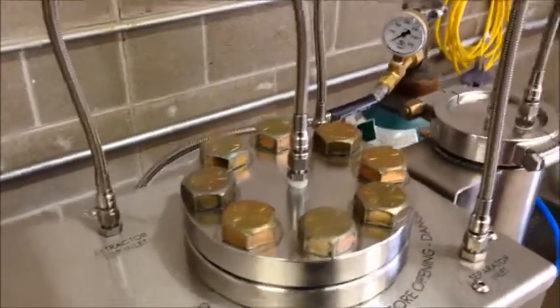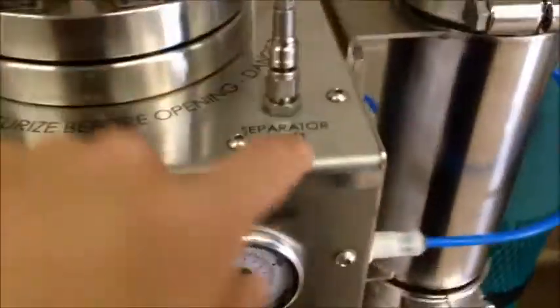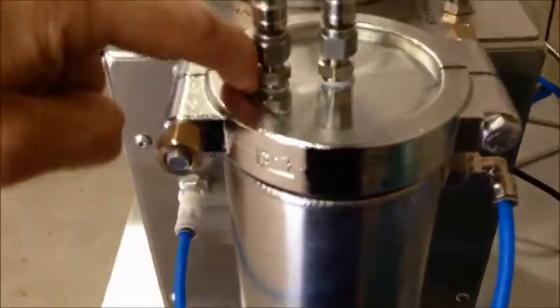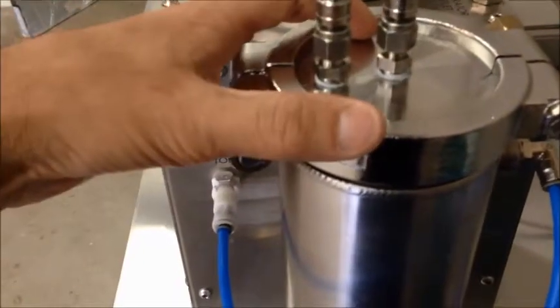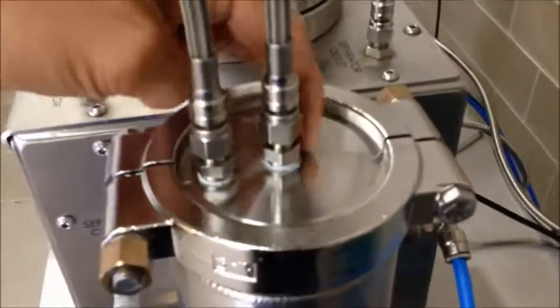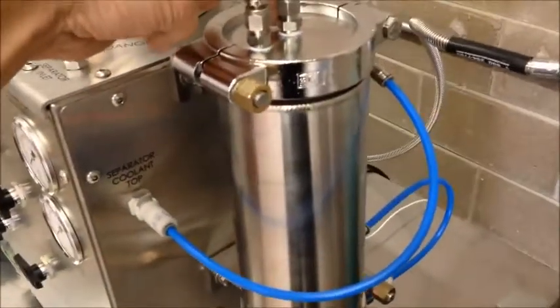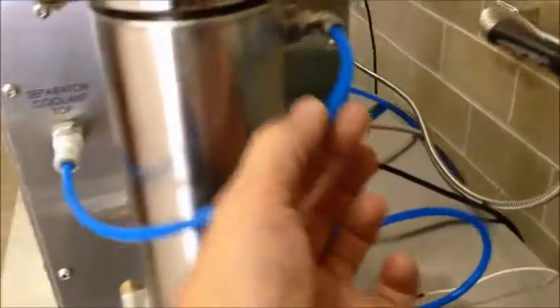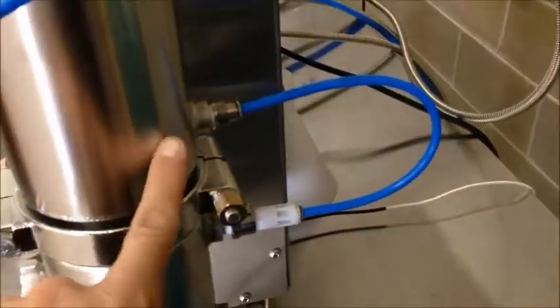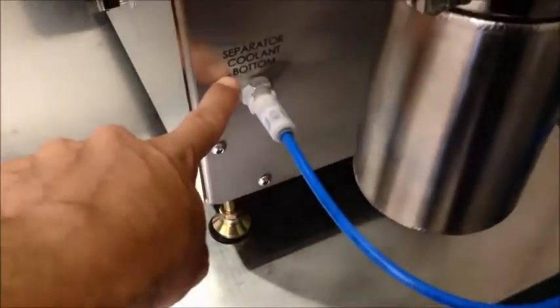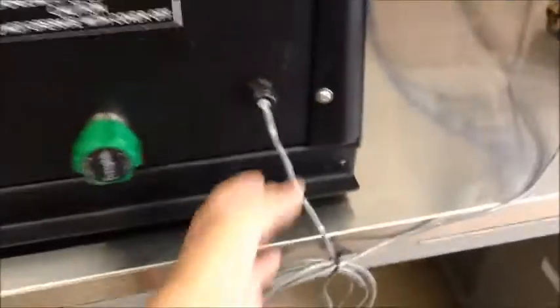extractor top inlet goes straight into the extractor. Separator inlet will go on the outer portion of this diameter. And separator outlet goes to the center hole on the top of your separator. Your separator coolant top comes straight to the top of the separator. And you have this one connecting the bottom of the separator to the collection cup. The bottom of the collection cup then goes to separator coolant bottom. Over here on the pump, you have this cord hanging out. Connect it right here. It screws in right below the computer.